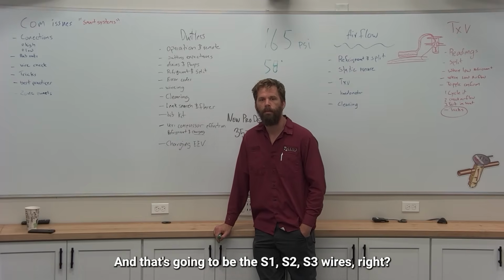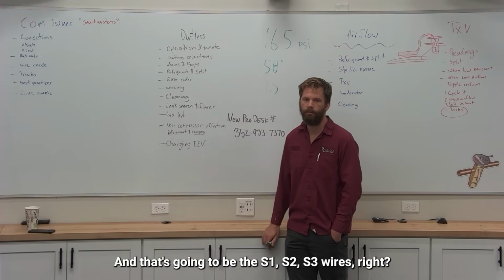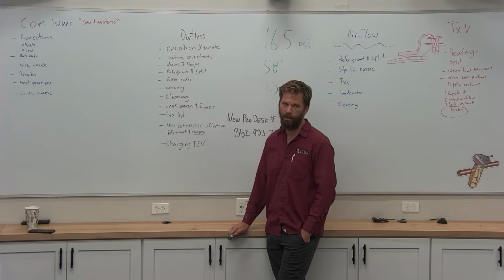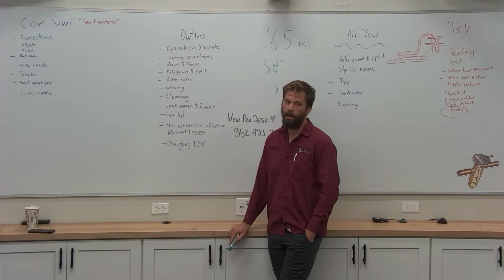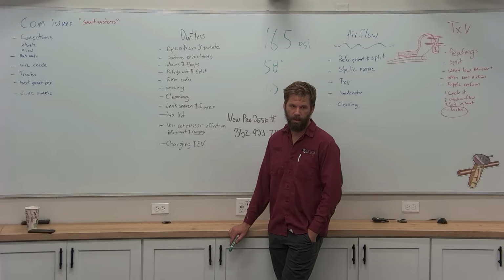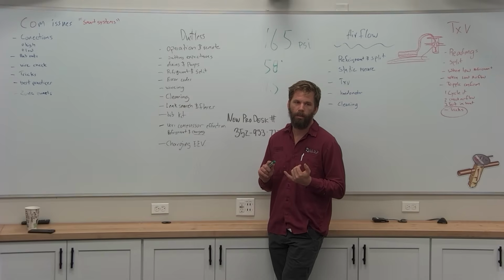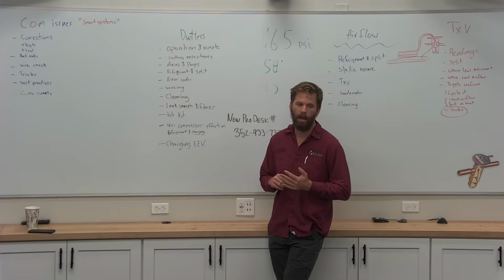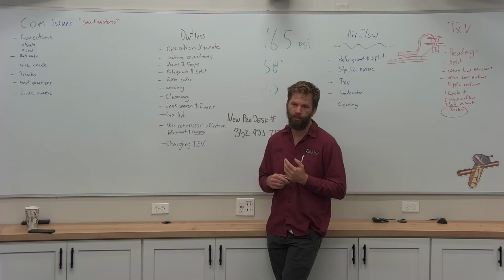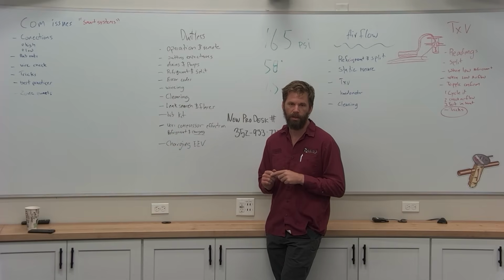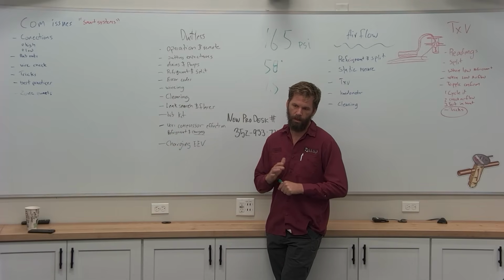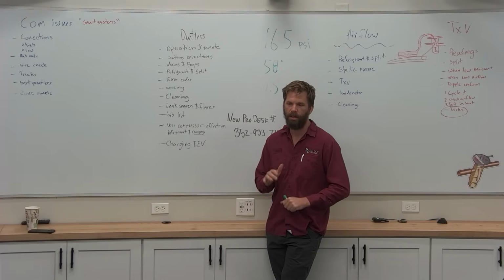And that's gonna be the S1, S2, S3 wires, right? Yeah, exactly. And then understanding if there's anything else that could be breaking those wire connections, like a safety tied into the pump or a humidistat relay that we put on to pass inspection. So there's a lot of other things that could be there. You have to slow down and just trace that wire and follow all of its connection points.